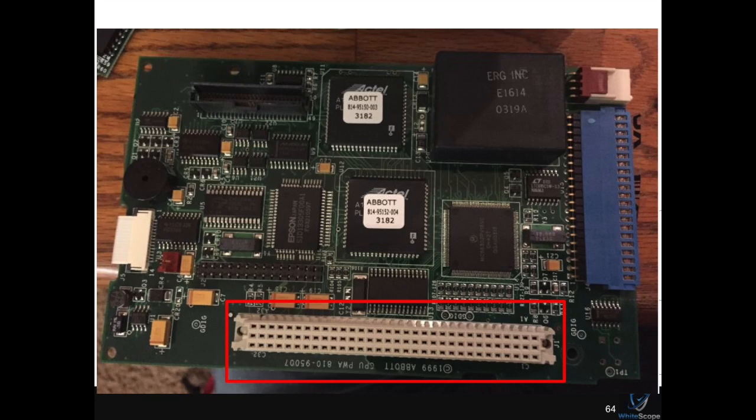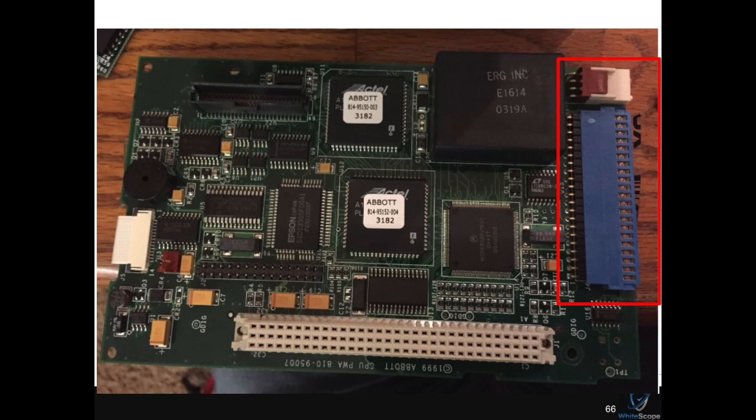The main board for this particular pump is a lot more simple, right? It's got some FPGAs on there, and of course there's the Eurocard connector down here. And then in order to drive the actual actuators that are going to cause the fluid to go through the IV lines, you're going to be using this interface right here, right? So if you're working backwards and saying, hey, how do I actuate this pump to do something it's not supposed to, you're going to want to know how to trigger this interface through the communications port, which is going to communicate over this Eurocard connector. Oh, and this last piece right here is power. This is how the pump gets power.